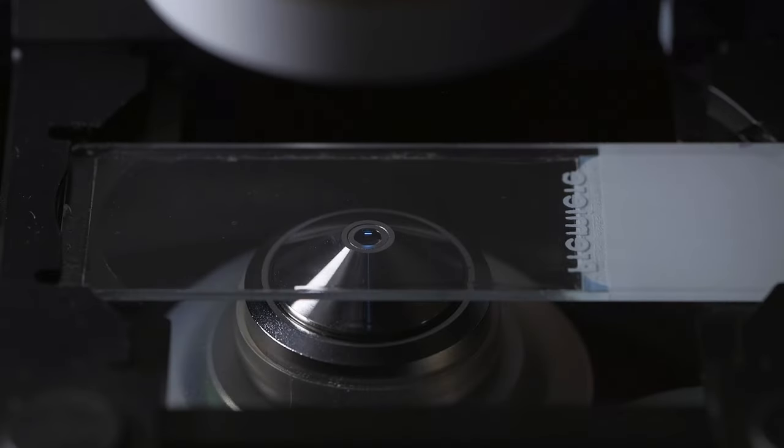So that's all great, in theory we can just insert a pinhole into a conjugate focal plane and take pictures just like we did with our traditional epifluorescence microscope, right? If you just insert a pinhole into a widefield microscope and attempt to visualize the image using point source illumination through the eyepieces, you would only see a tiny spot of fluorescence signal smack dab in the middle of the field of view. The confocal effect only works on a very small spot in our field of view at any one time. So how do we get an image with a confocal then? We have to move that tiny little spot around our field of view to build an image. This is called scanning.